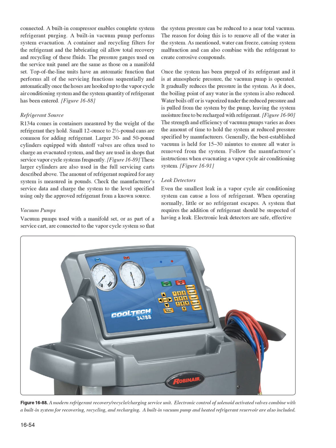Figure 16-90, the strength and efficiency of vacuum pumps varies, as does the amount of time to hold the system at reduced pressure specified by manufacturers. Generally, the best established vacuum is held for 15 to 30 minutes to ensure all water is removed from the system. Follow the manufacturer's instructions when evacuating a vapor cycle air conditioning system.